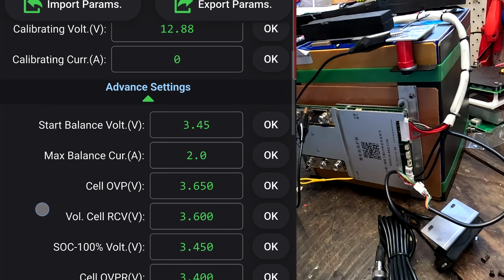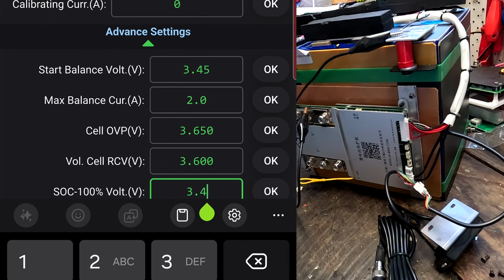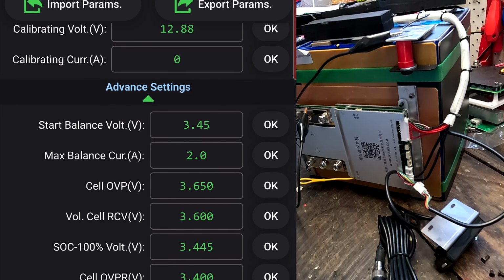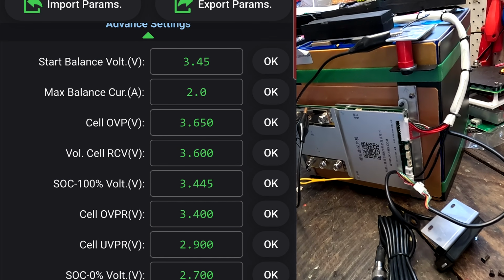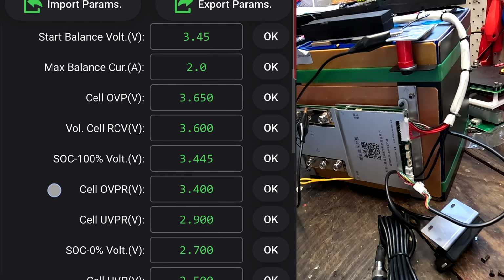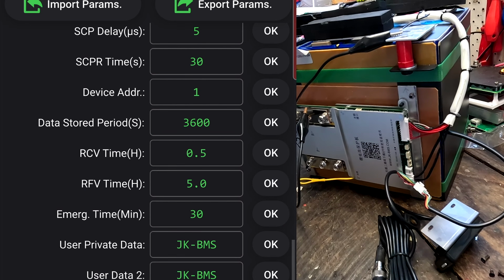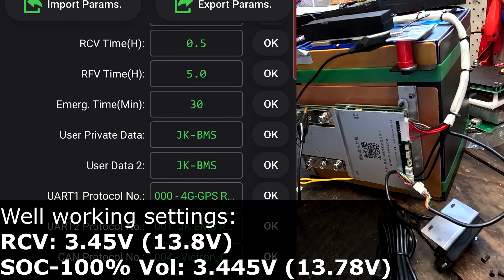I think we have to change this back again here to 3.45. Because if we set the charge controller to 13.8 volt, which is 3.45, the cells will not be sitting at 3.45 all the time, especially not if they are load connected, yeah? So there's voltages going up and down a little bit, and if it goes under 3.45 volts, the timer is not running. So it will never reach this half an hour of absorption time, and then it will never reset. So you set your 100% reset voltage a little bit lower to what you actually charge to.